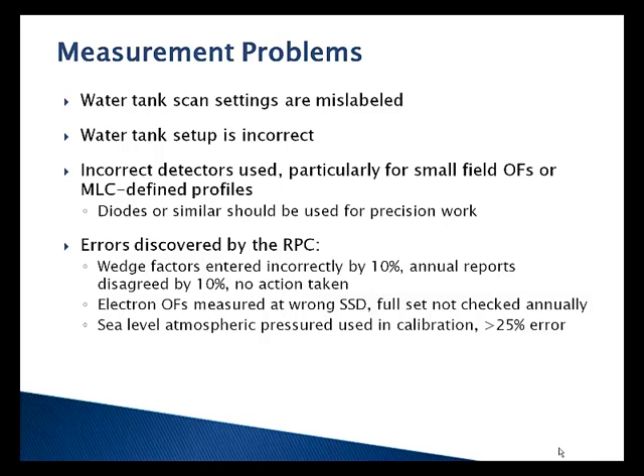So I talked to some people at the RPC. I said, what sort of measurement problems have you guys discovered? One clinic had wedge factors incorrectly entered in their planning system by 10%. RPC measured that. They found there's a 10% error. They looked back at the annual QA. The physicist has caught that every single year. He caught that it was 10% off, but nothing was corrected.